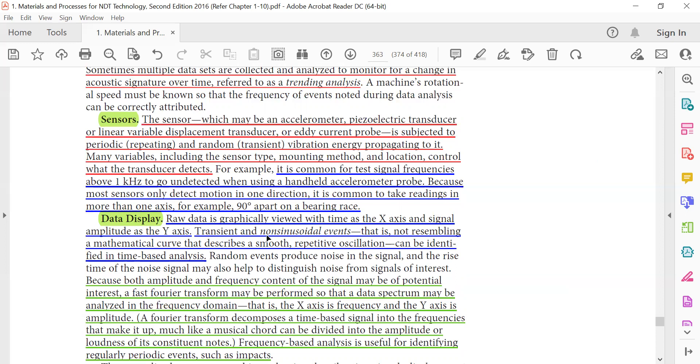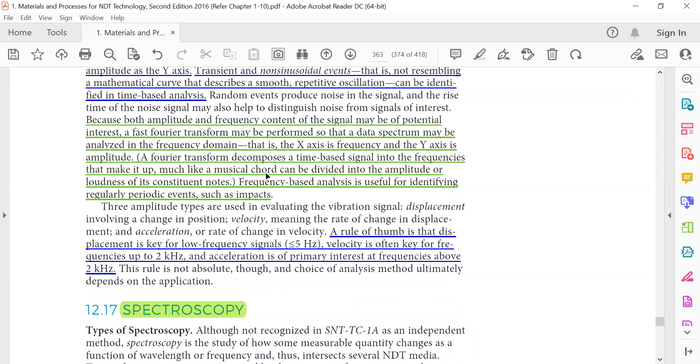Data display: raw data is graphically viewed with time as the x-axis and signal amplitude as the y-axis. Transient and non-sinusoidal signals that do not resemble a mathematical curve describing a smooth repetitive oscillation can be identified with time-based analysis. Because both amplitude and frequency content of the signal may be of potential interest, a fast Fourier transform may be performed so that the data spectrum may be analyzed in the frequency domain. The x-axis is the frequency and the y-axis is the amplitude. A Fourier transformation decomposes a time-based signal into the different frequencies that make it up.